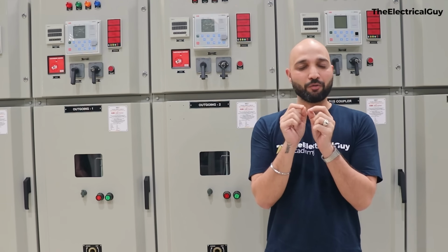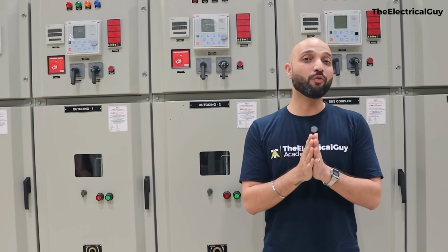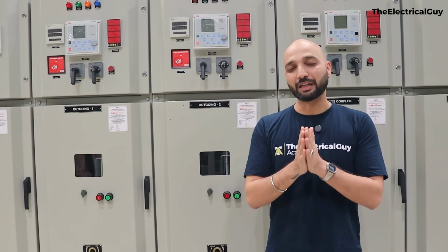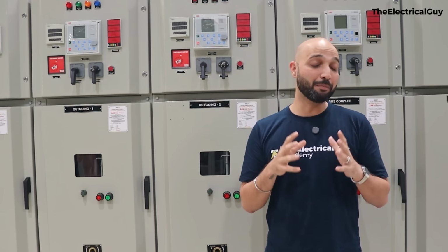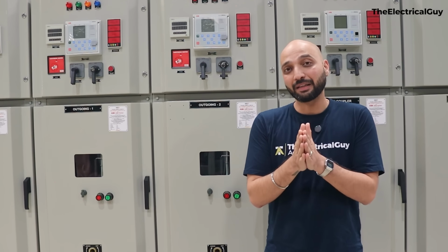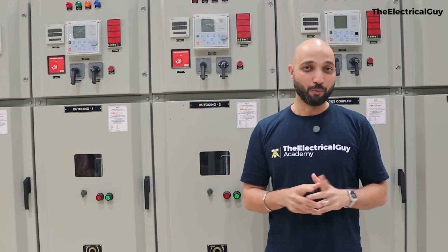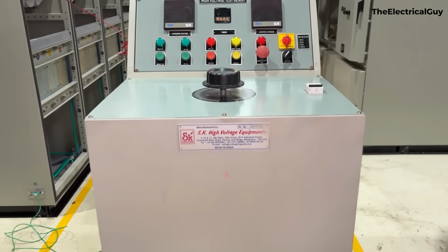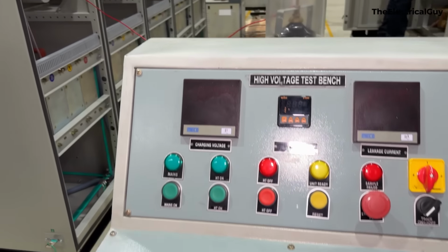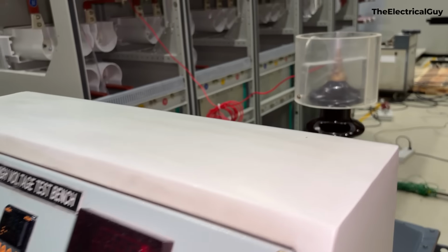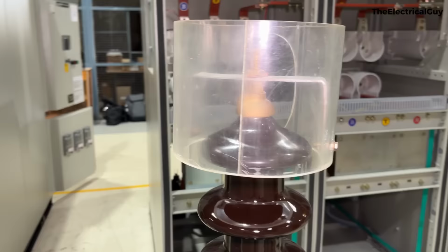Now it's very important. Now we have seen the complete lineup, but how do we make sure that these panels are good enough for our supply? Will they be able to take the high voltage that is occurring in the system? Well, to make sure the panels are good, the insulation strength of the panels are good, we perform the high voltage test on it. It's also called as the power frequency withstand test.